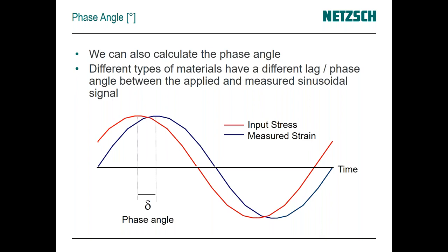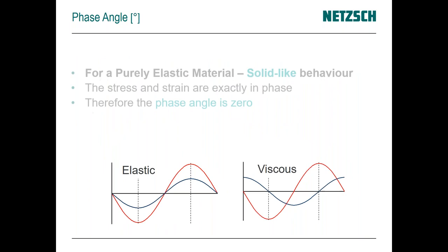Phase angle is a new component we're going to discuss. It represents whatever lag is associated with applying a force to the material — we apply a strain and see the resultant movement from the sample, and different types of materials have different lags. The difference in how the load responds relates to the viscoelastic properties in the material.